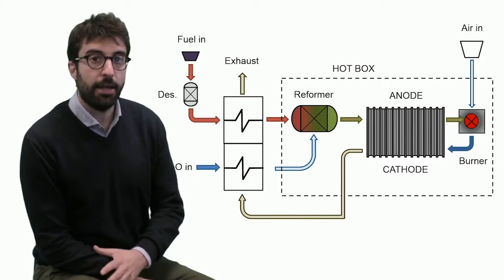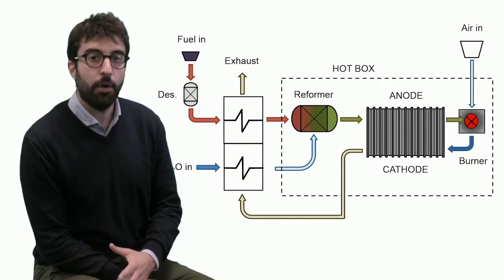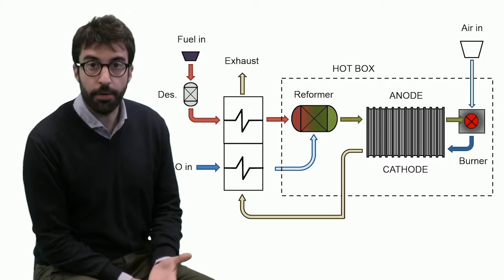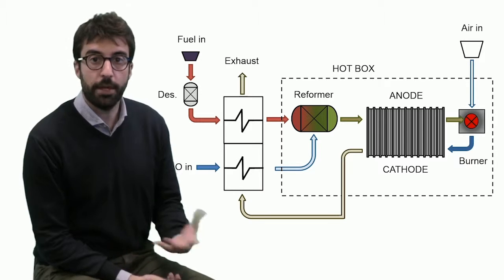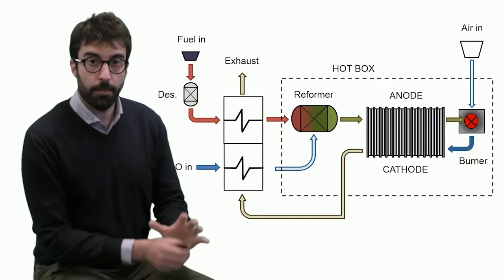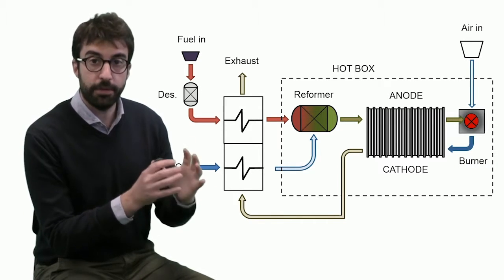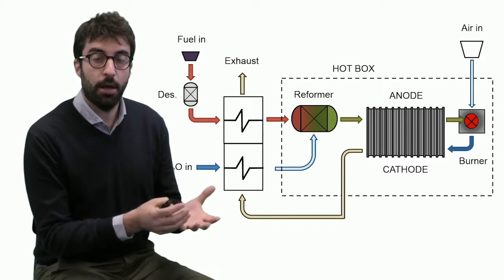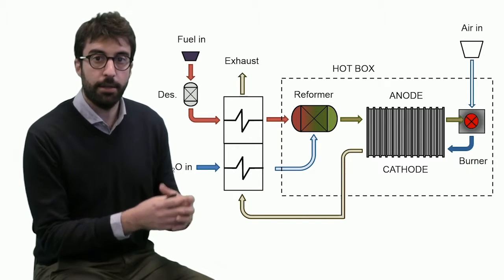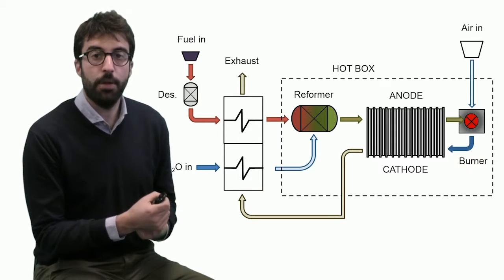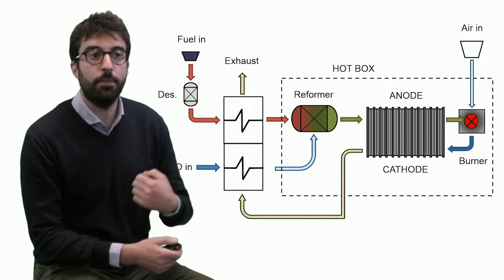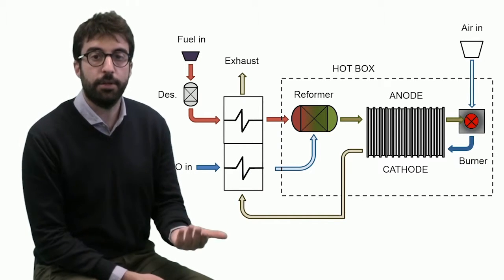In general, we can identify an area called hot box that involves all the high temperature operating systems: the reformer, the stack, and the burner. Usually we can optimize thermal equilibrium of these three components that improves the thermal stability, since for example the reformer is an endothermic reactor while the burner is an exothermic reactor. But what is required is very high quality optimization.